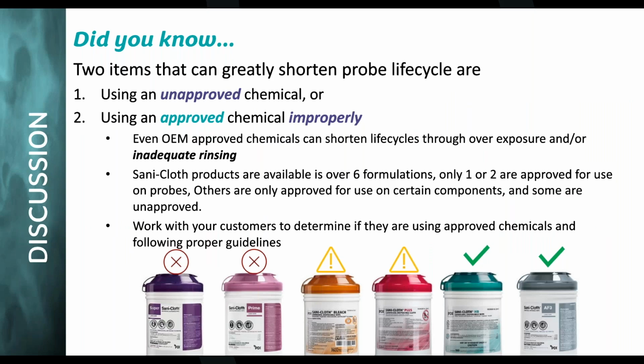Or people use an approved chemical improperly. We have a program called Safety where we teach hospitals how to mitigate transesophageal damage. And I visited a site not long ago, and they were using an approved chemical. It's called glutaraldehyde. It's a very good disinfectant. It's nasty. And I said, so, what's going on? They said, well, we use this chemical, and then they got defensive. We use the right chemicals. I'm like, how long are you soaking it for? In between patients. How long is that? Well, sometimes it's 10 minutes, sometimes it's a weekend. And so they were leaving the probe in this chemical for 48 hours sometimes, which was killing the probe. The instructions for use for that chemical was 12 minutes, and then you have to do a clean water rinse to get rid of all residue. And they were leaving it in for 48 hours. So they were using an approved chemical, but they weren't using it correctly.